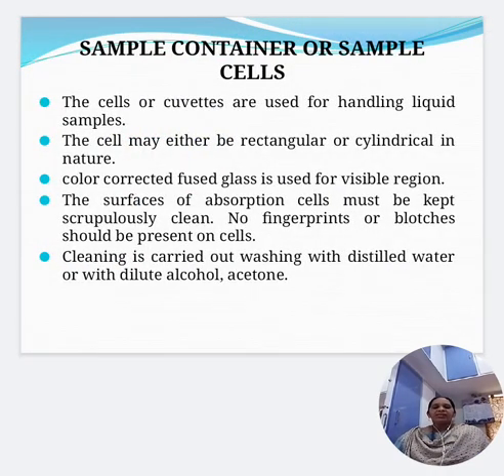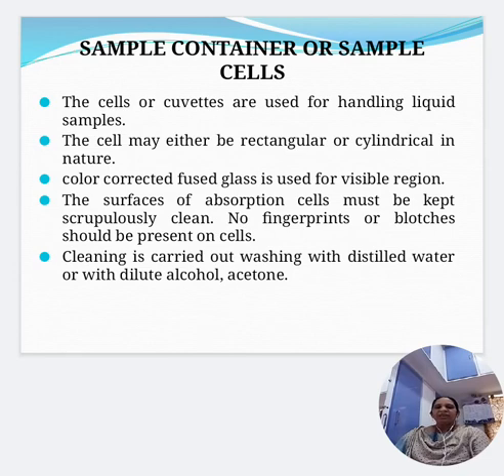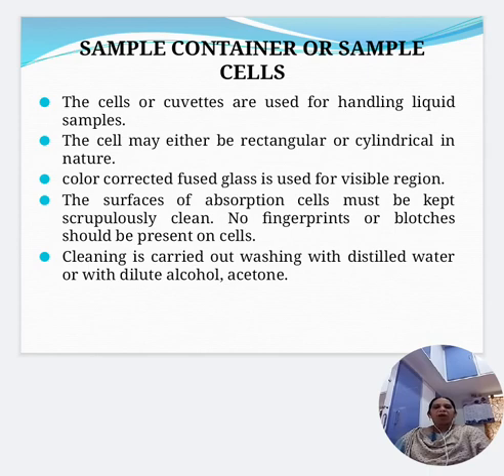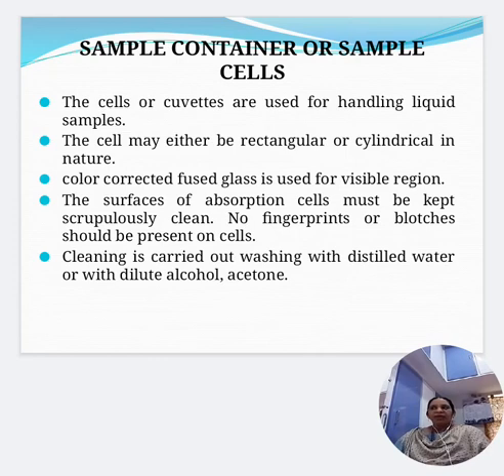The sample container or cuvette is used for handling liquid samples. Cells may be either rectangular or cylindrical. Color-corrected fused glass is used for the visible region. The surface of the absorption cells must be kept scrupulously clean — no fingerprints or blotches should be present, as these cause errors. Cleaning is carried out by washing with distilled water, dilute alcohol, or acetone.